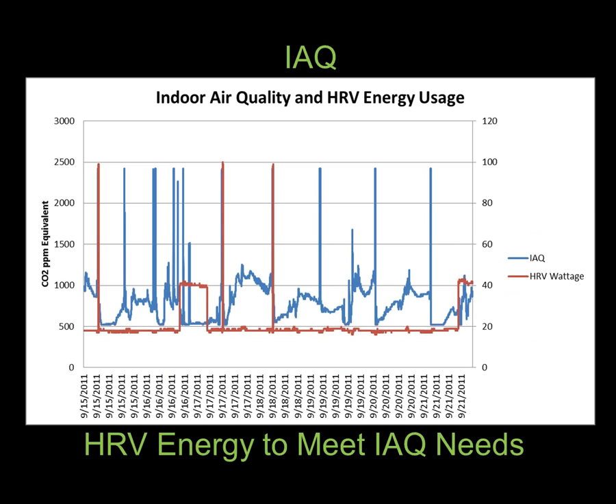Indoor air quality, I think, is a critical component to any passive house building, and one of those nice results that you get from focusing on things like energy reduction. Here you can see the indoor air quality as measured in the building consistently below 1,000 parts per million, and then the wattage to run this unit. When it's in continuous operation, it's about 18 watts continuous, which is the equivalent of a fairly good-sized CFL light bulb. So we're not talking a lot of energy to run this unit.